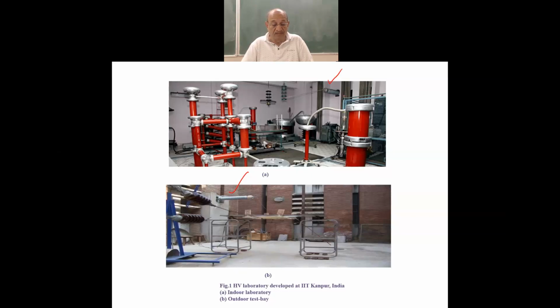In the open air bay, as you see here, the two insulator strings on the left side are at the moment stretching a 25 kV traction catenary. The electric traction 25 kV catenary has been stretched in the open air, and the clearance to the ground from the high voltage conductors of the traction is being investigated with this experimental setup.